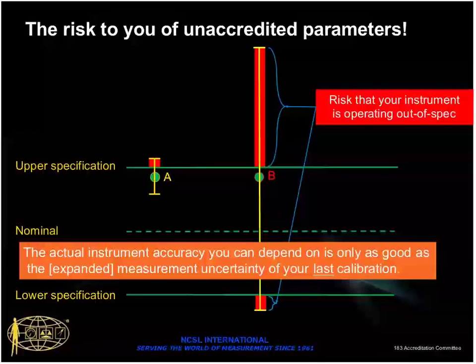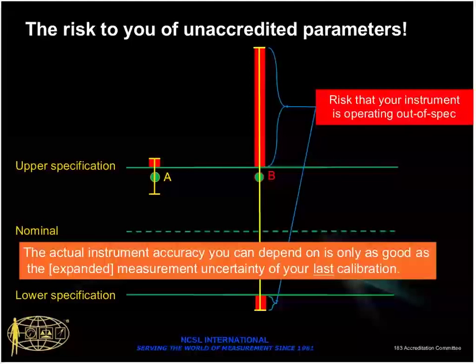And what I'm telling you is that in my practical experience, oftentimes when I'm asked as a technical consultant to look at the differences between calibration measurements between two different laboratories, I find that sometimes they don't even include a measurement in the report, so I don't know if they made the measurement or not. But when I look at the trace information, I can at least see which instrument they used. And having been a long-term employee of HP, I know those instrument block diagrams well enough.